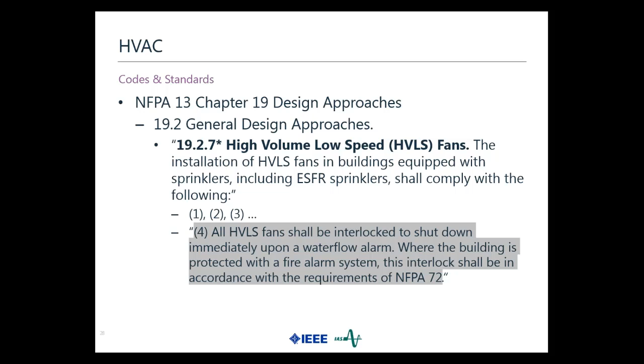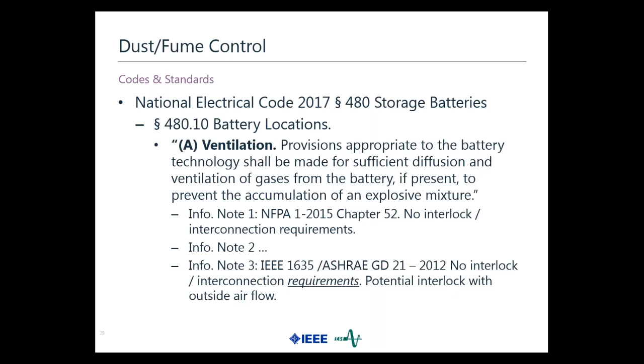Yes, I've jumped back to the NEC, but in the NEC under batteries, we get referred to a couple of other standards in the informational notes. One, NFPA 1, which is not adopted by the State Fire Marshal, by the way. There are no interlock interconnection requirements. And then there's an IEEE cross-listed with an ASHRAE Guide 21. There's no requirements, but it does mention potentially interlocking your battery charger with outside airflow.